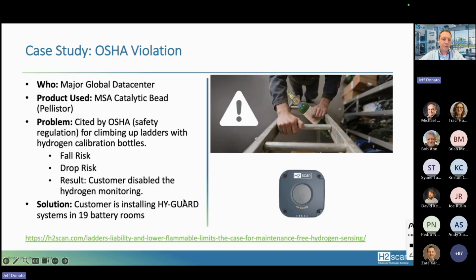This resulted in the customer disabling their hydrogen monitoring because they were not allowed to climb the ladders anymore to get to the sensors. Their sensors drifted and started not working, basically. So they disabled those sensors, and the customer is now installing HY-GUARD systems in 19 battery rooms in just this one facility, and then they're going to continue on to other facilities throughout the country and then also throughout the world.